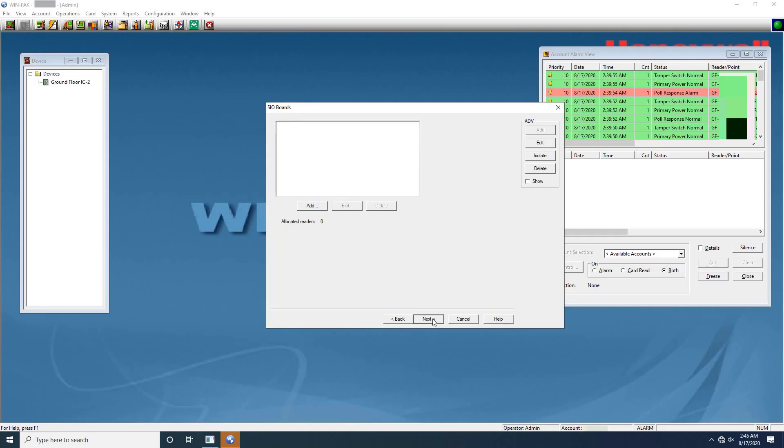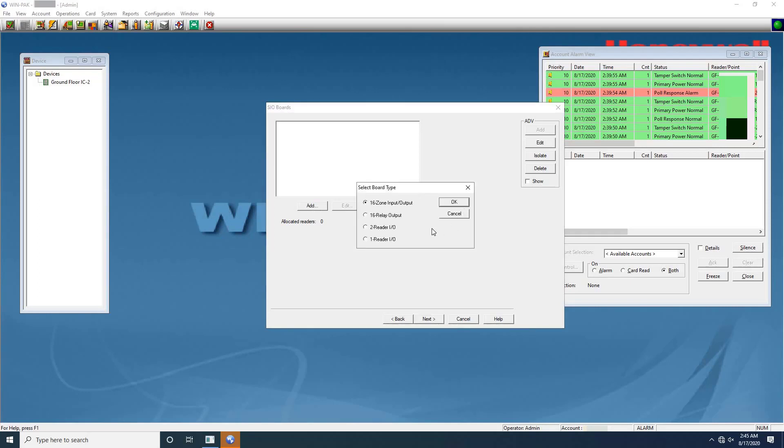Click next to add SIO boards to intelligent controller. The number of readers, inputs, and outputs that can be connected to the controller is based on the type of SIO board that is added to the intelligent controller. In the P-series configuration SIO boards dialog box, click on add button. The select board type dialog box appears for user to select the SIO board. The available SIO board types are 16 zone input and output, 16 relay output, 2 reader IO, and 1 reader IO.